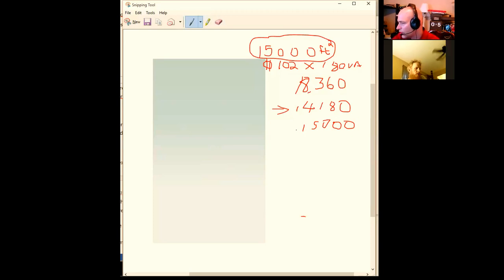So section 1 is every 5-foot section plus any fraction is going to be counted as one count. So if you end up with a 6-foot section, that's actually going to be 2 counts, because it's the 5-foot piece plus the 1 foot counts as a whole 5-foot section. And you don't want to add those up first. You want to do them individually, each piece, and then convert them to counts and then multiply times 180 VA.